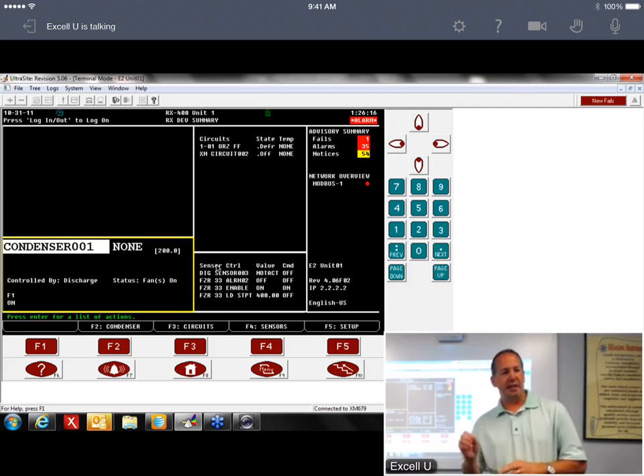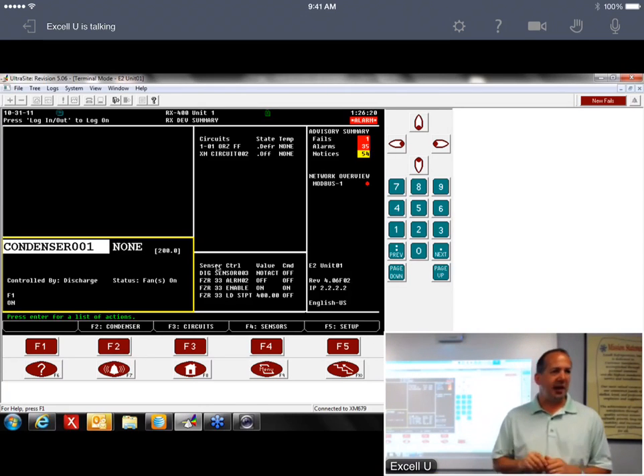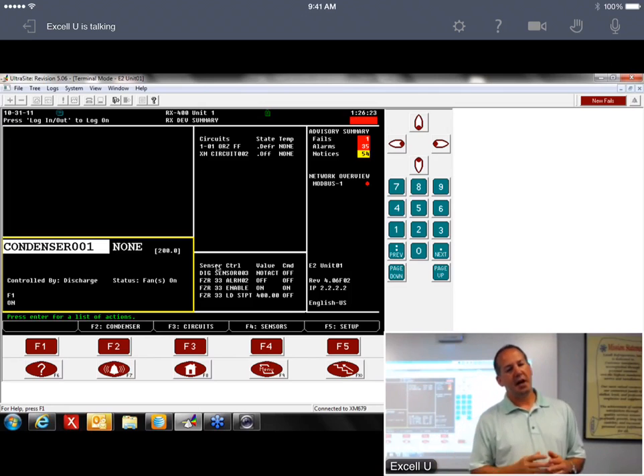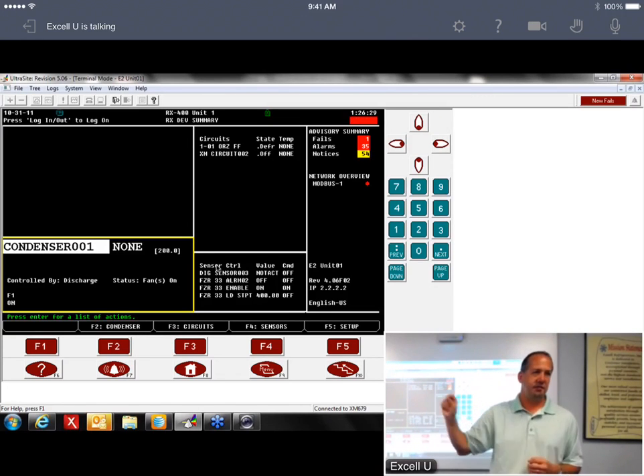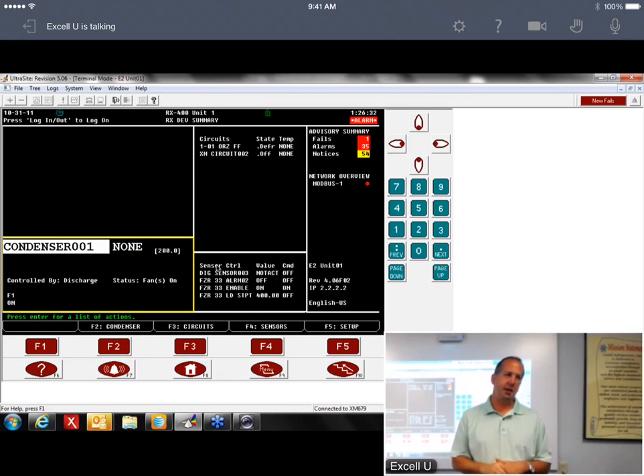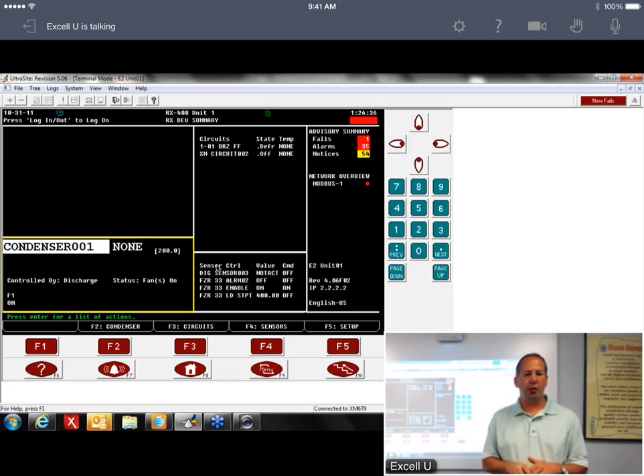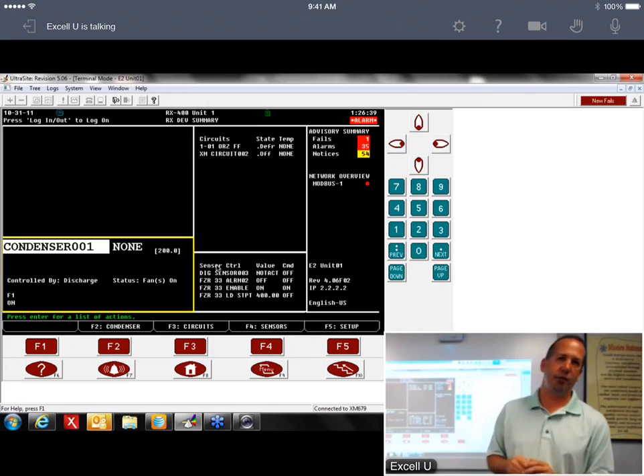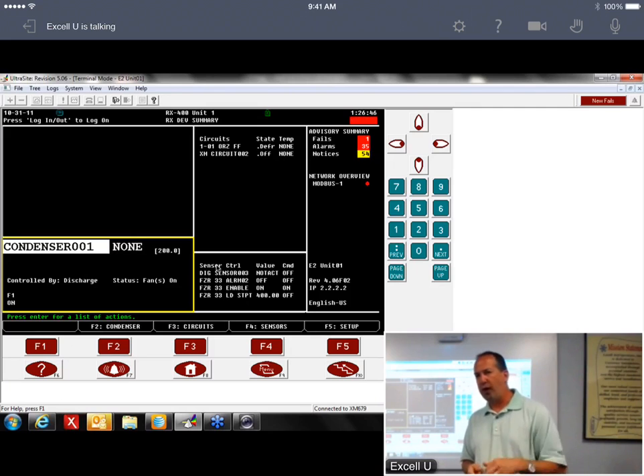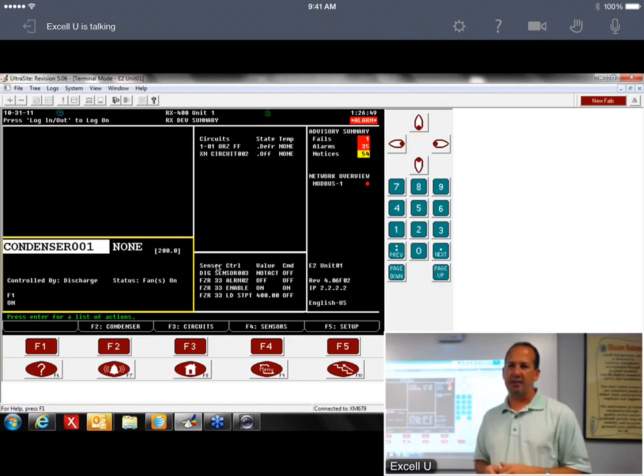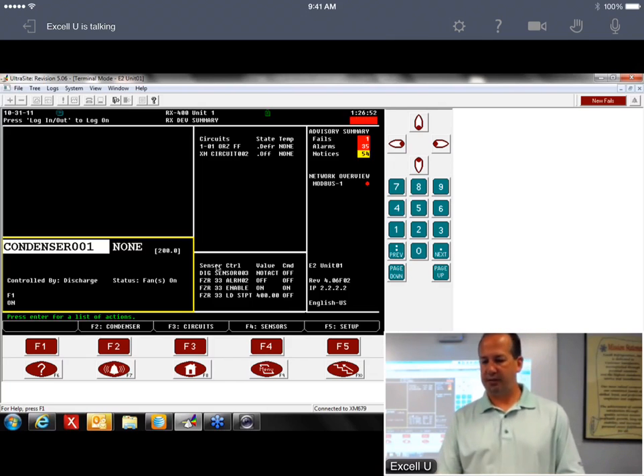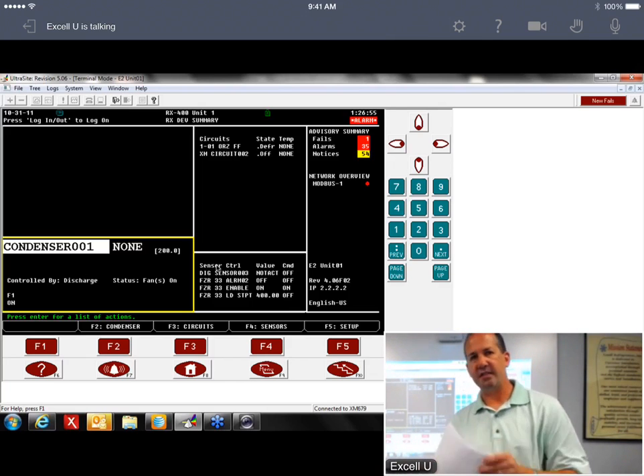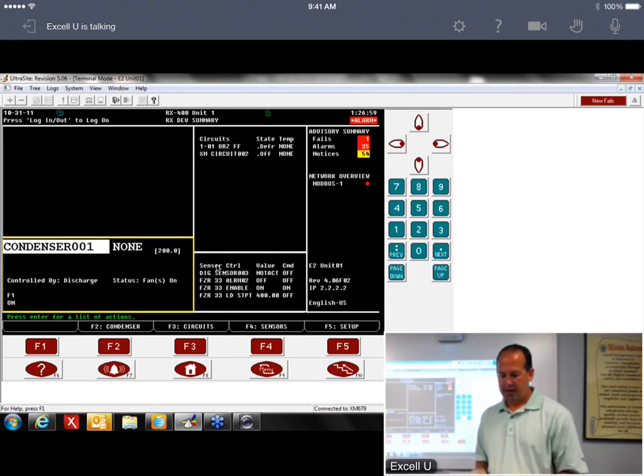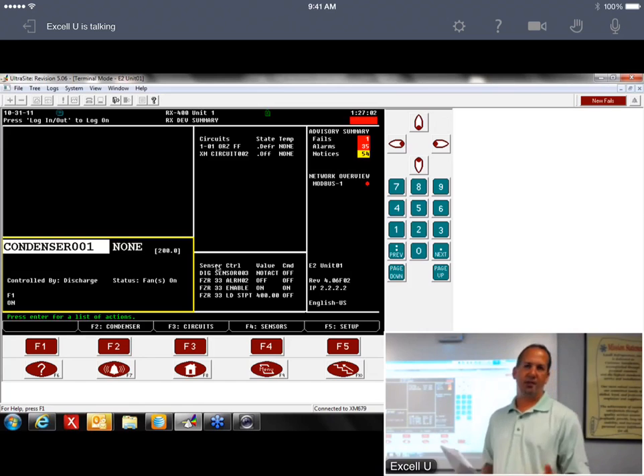One thing too is the case lights. The schedule for case lights resides in the BX in most of your stores. The XM devices cannot read that schedule in BX, so if you try to go out and grab that schedule out of the BX through global data, you're not going to be able to do it. So what we do is create a time schedule for the case lights in the E2, and then we point to that one. If you have case control storage, you'll have a lighting schedule that resides in the E2 and the RX controller, the refrigeration controller. It walks you through how to set it up — it's not real hard, it's got step-by-step procedures to do that. From what I've been told, the CCB and the CC100 were the same way.